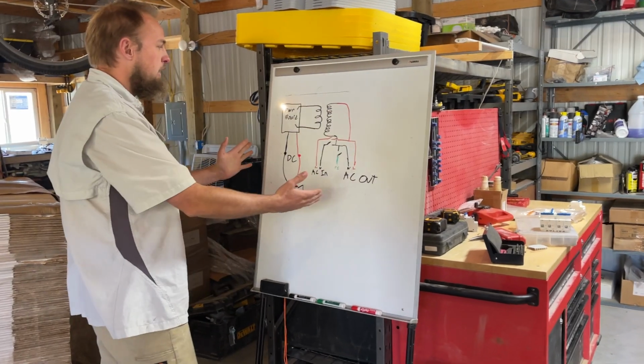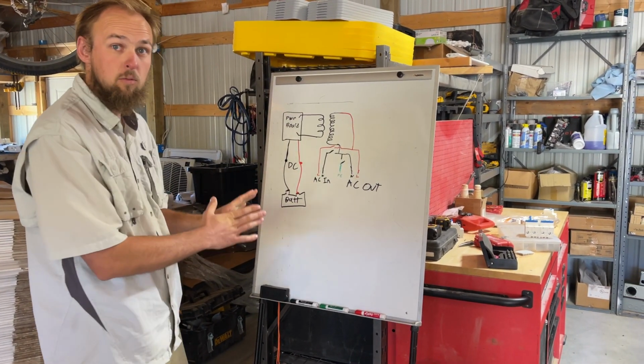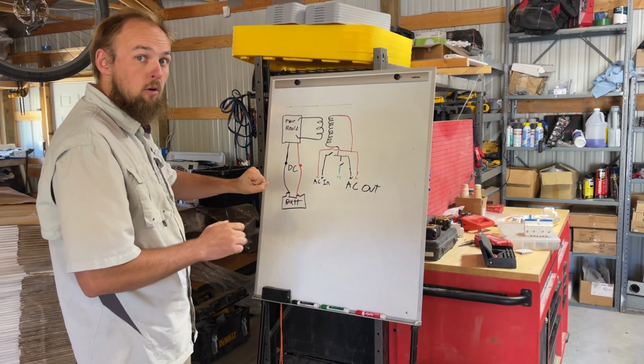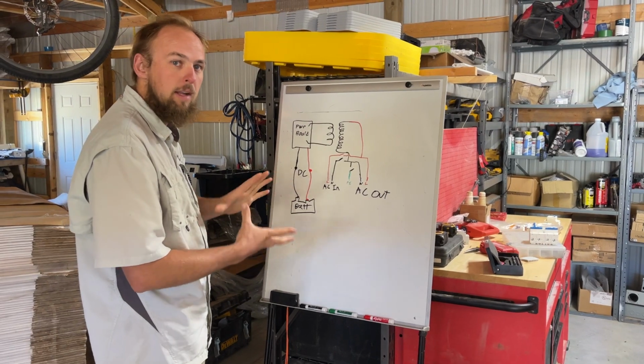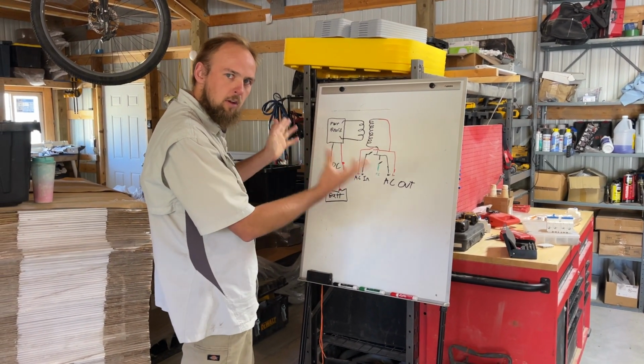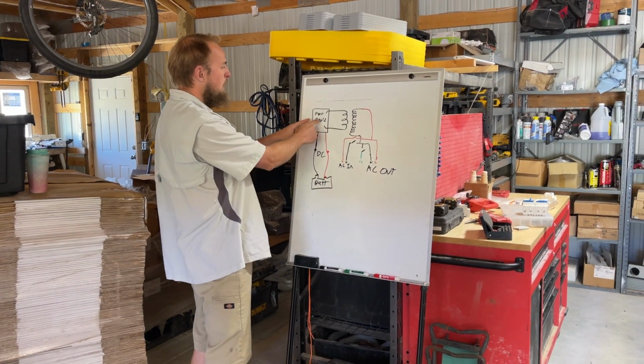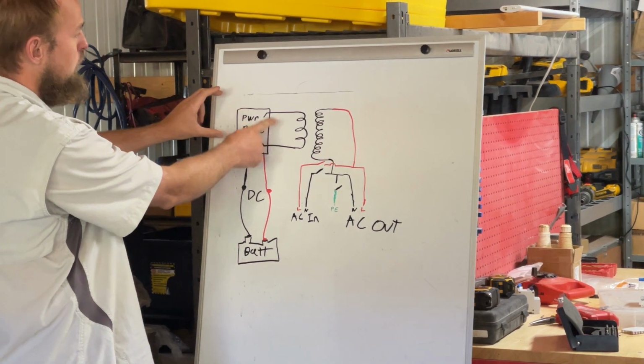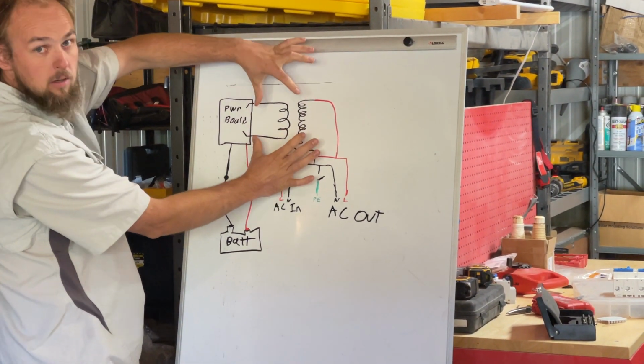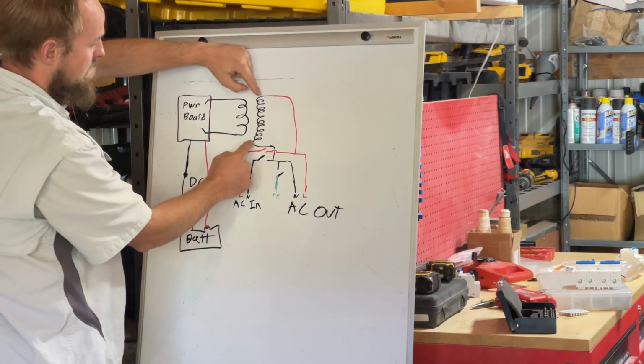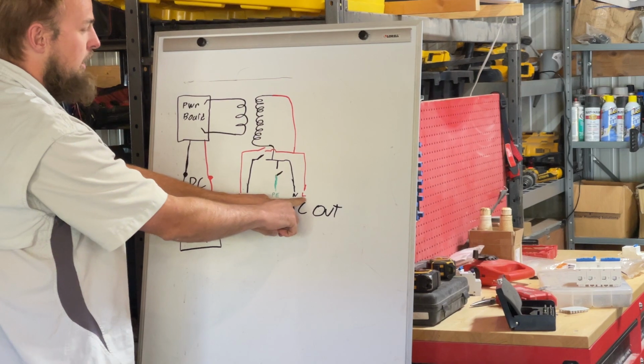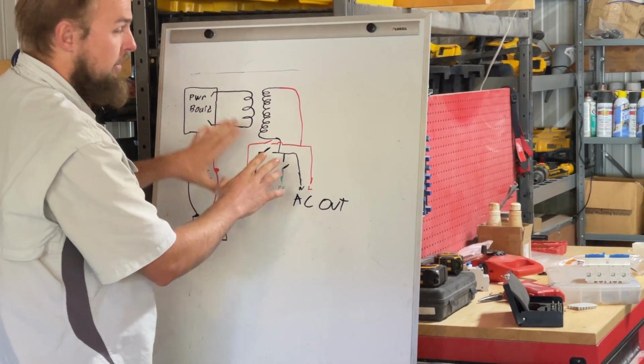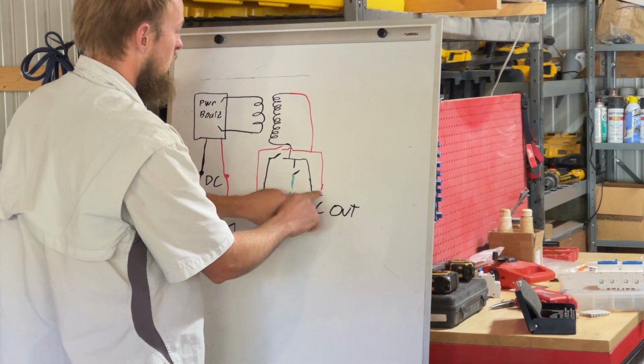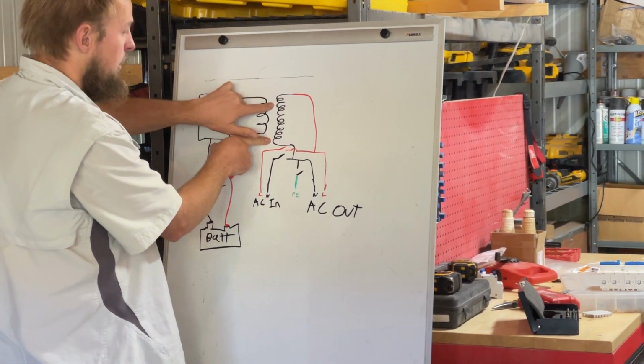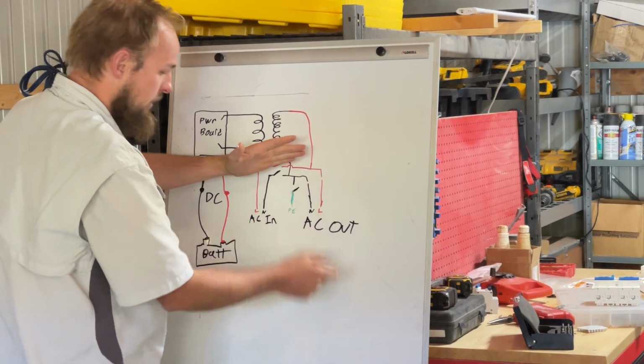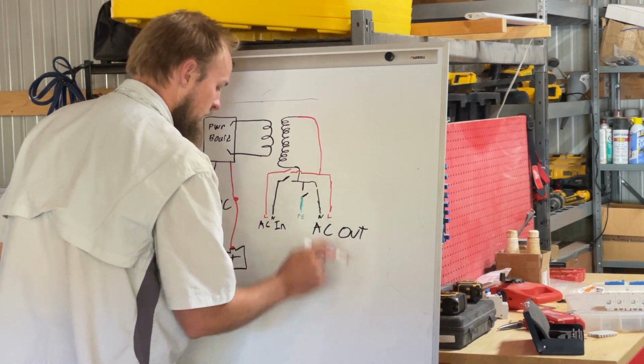So this here is a diagram of the internals of an inverter. Of course, there's a lot of things missing, but it's your basic topology for all of your low frequency inverters, like your Victron, Outback, and all of those. This one is specifically for Victron, but it's all very similar. You've got your battery that goes to a power board, in DC power that's converting to a low voltage AC, going to the transformer, which is converting that low voltage AC to high voltage AC, and that connects to your line and neutral output. So when the inverter is turned off, your line and neutral are often connected directly to the transformer still. There may be some inverters that have a contactor here, but generally speaking, that's still connected.